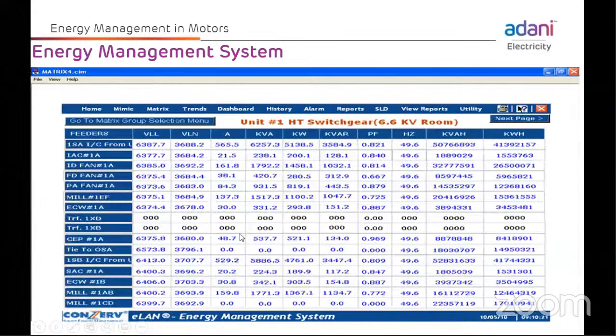Next, you can see here all the HT switchgear data. Compressors, ID fan, PA fan, everything - we instantly get the readings of this. From that basis, we can analyze immediately and do corrective action on a shift basis, daily basis, or monthly basis. But on a one day basis, it is possible to save energy based on online data, because we install all the meters, 350 meters in the systems, and that data is collected at one place only.